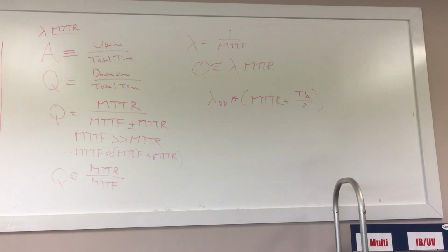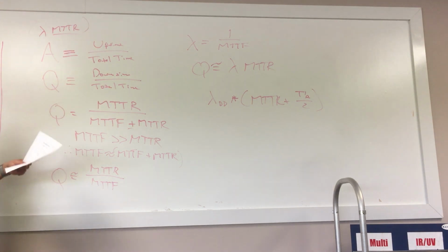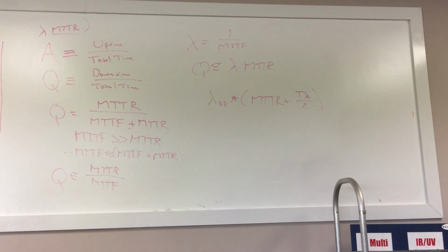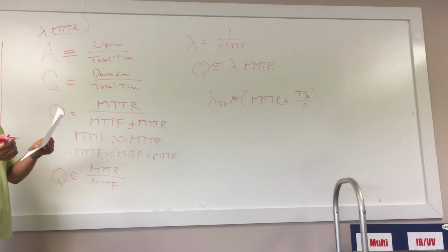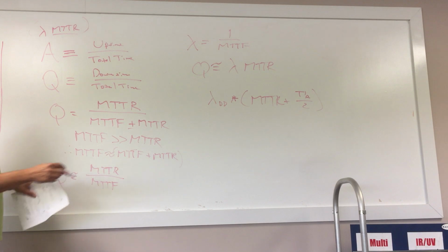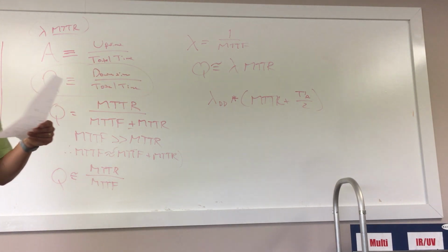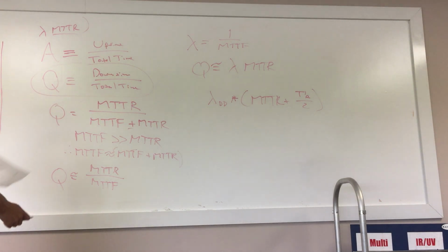So this is where all of these equations came from. Term 1, the DD term, is your traditional unavailability. Term 2 is your traditional unreliability due to undetected failures. Term 3 is your never detected, which is still an unreliability. And then the last term is this format of the unavailability equation, and that's the online testing term. So that's where the first row came from. 1 out of 1.